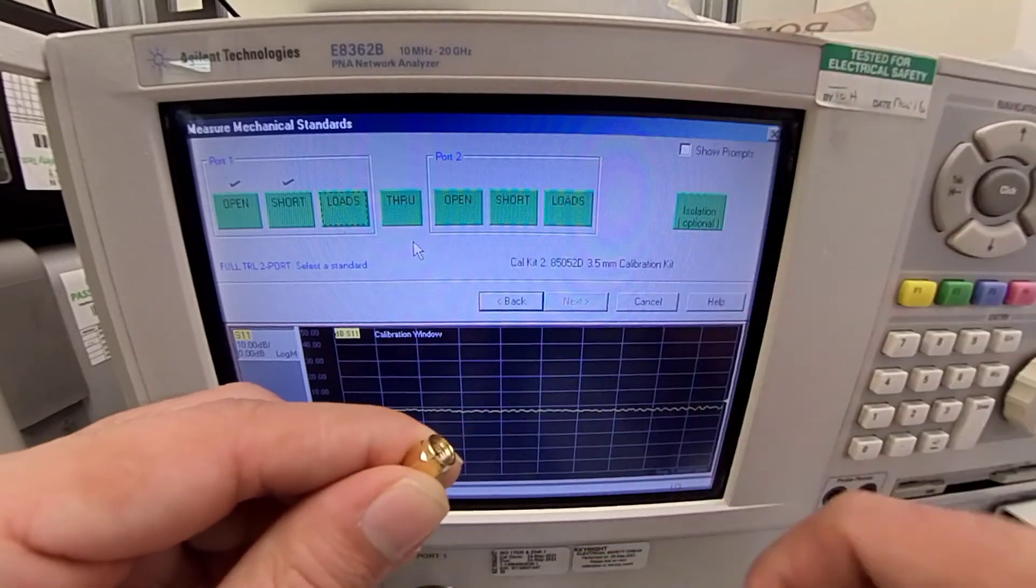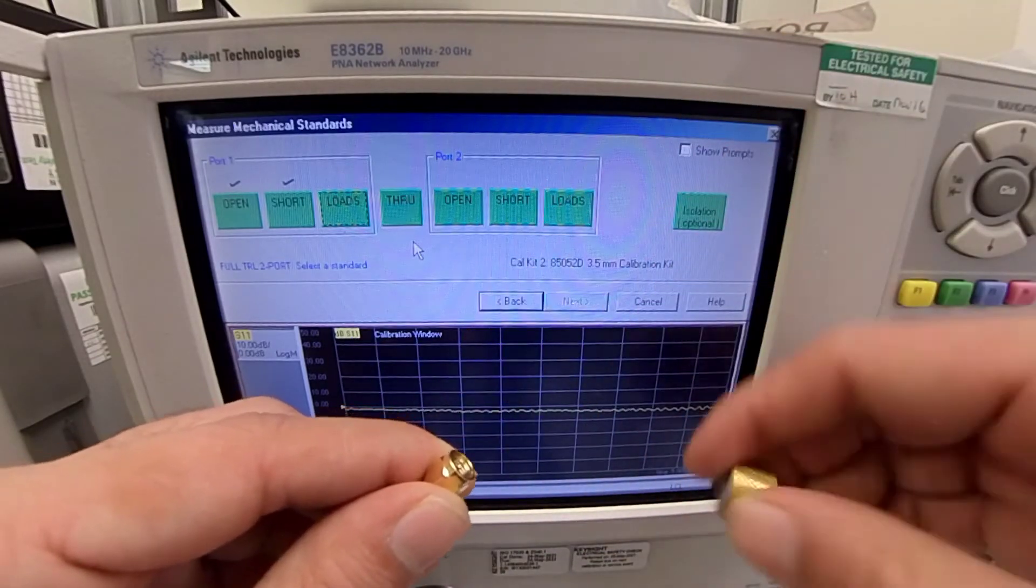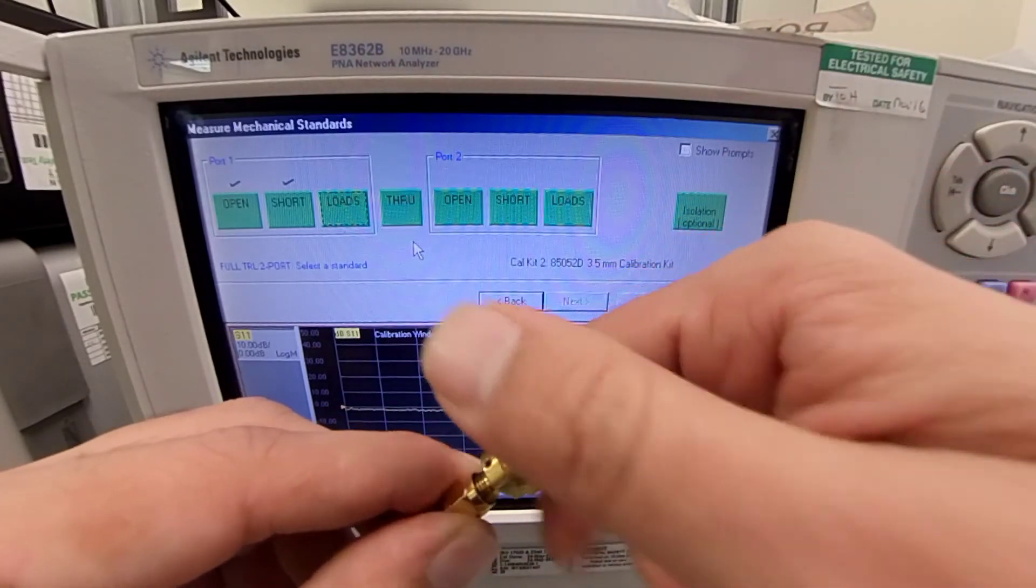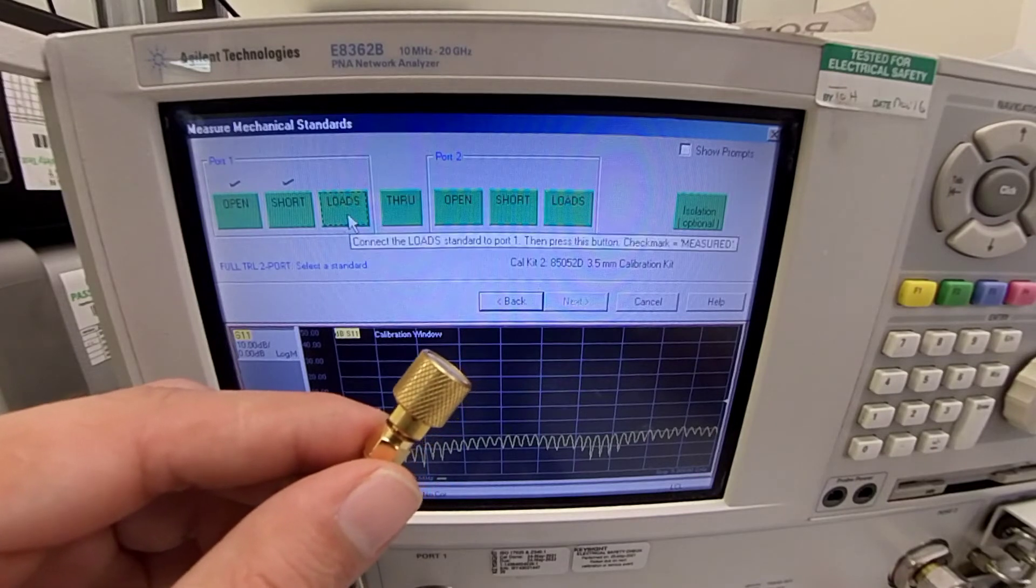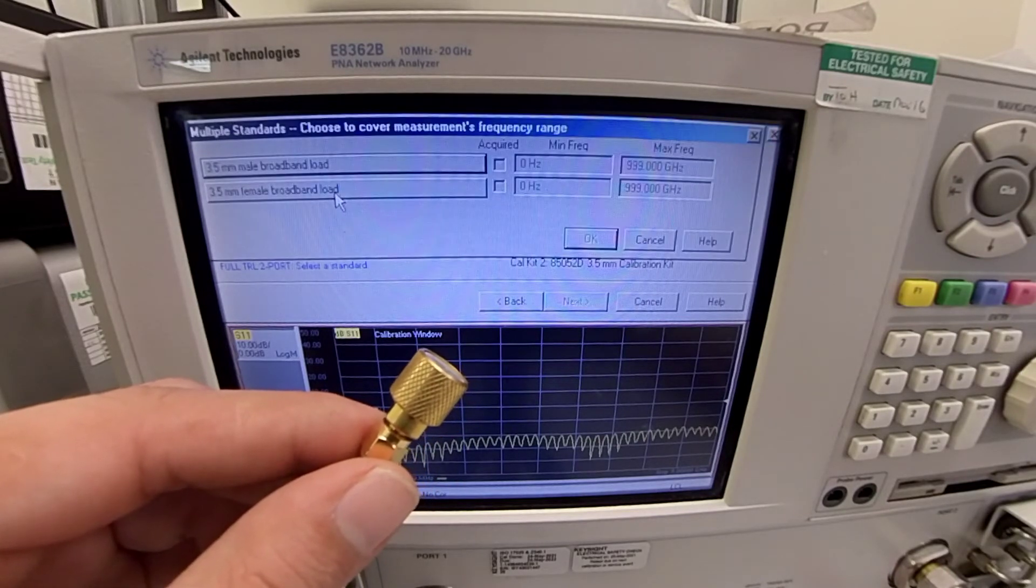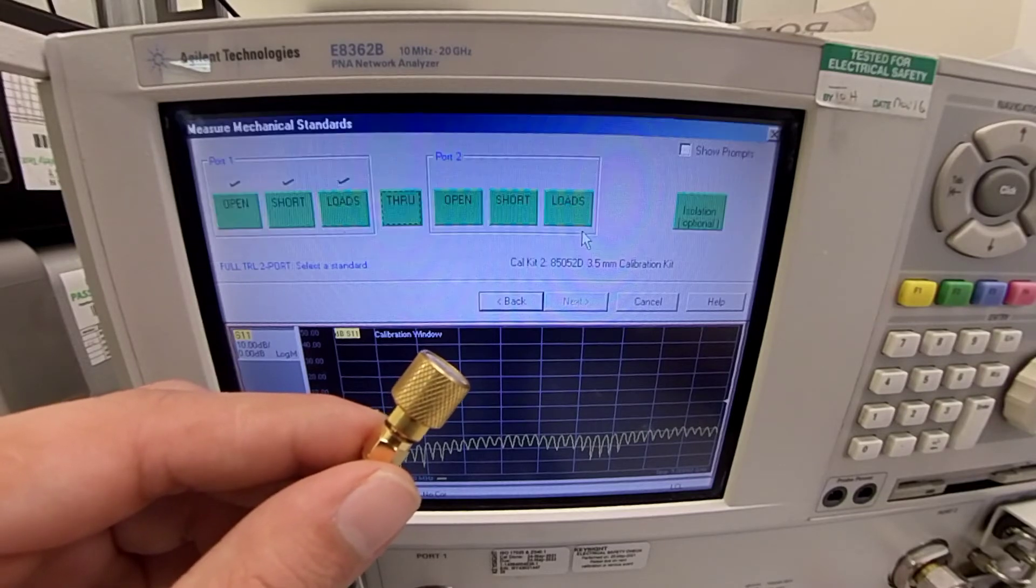Now, we replace this with the broadband load. Press on loads. Female, broadband load. Press OK. And we are done with the calibration of port number 1.